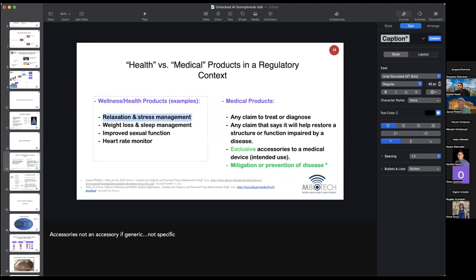Examples of health products include relaxation and stress management, sleep management, and improved sexual function. A heart rate monitor — that's going to depend. If you're using a heart rate monitor in a high-risk population, it'll be regulated as a medical product. If used in the general population, it'll be regulated as a health and wellness product. This all comes back to hazard analysis and risk. All of these things are low risk, but the heart rate monitor could become high risk if you're exclusively targeting high-risk patients.